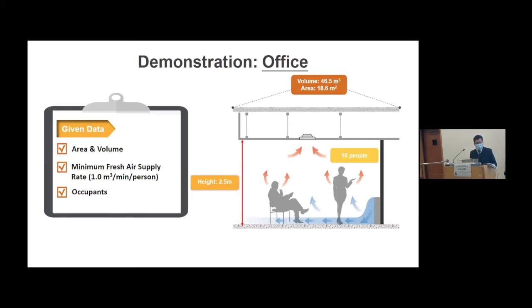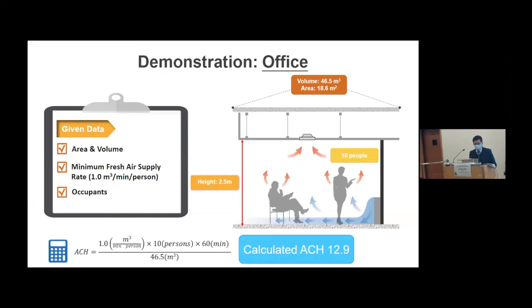So with a room of 46.5 cubic meters and using this formula, the minimum fresh air change rate per hour is approximately 12.9 ACH. This 12.9 ACH is in fact very good ventilation, as you will see later that the international standards specify a minimum of 12 ACH for hospital airborne isolation wards.